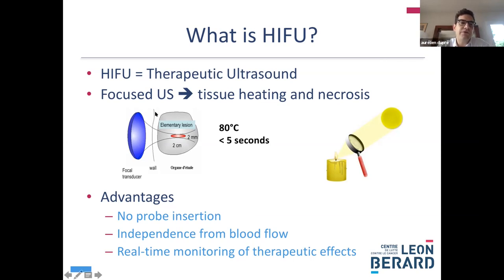It's the same principle with ultrasound. You have a focal transducer which focuses the ultrasound, and at the focal point you have an increase in temperature to 70 to 80 degrees in a few seconds, which results in coagulative necrosis.